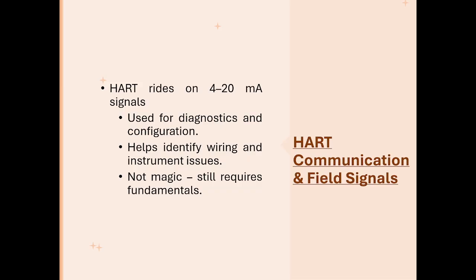However, this is very important, because HART does not replace good installation practices. If the wiring is poor, or the grounding is bad, or the loop is incorrectly connected, HART will not save you. The fundamentals always come first.